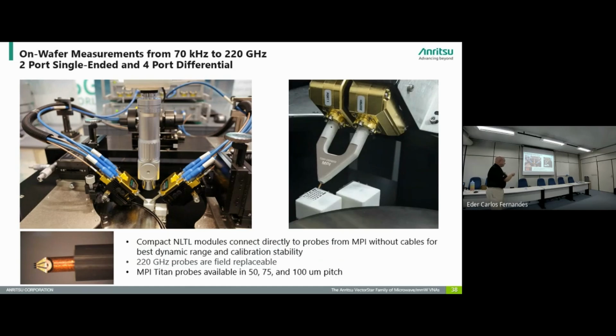So this by far is the most challenging setup I have worked on, up to 220 gigahertz on wafer, using a differential probe. These probes are typically, for these frequencies, the pitch between the ground signal ground is on the order of 50 to 75 to 100 microns. So they're pretty small. But again, we're still using a substrate that has all the standards on there.